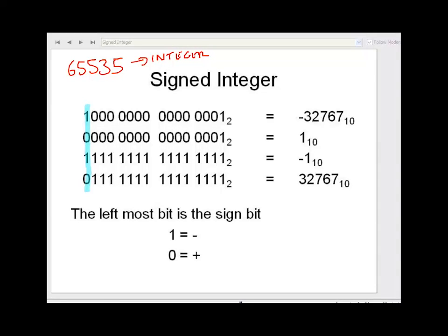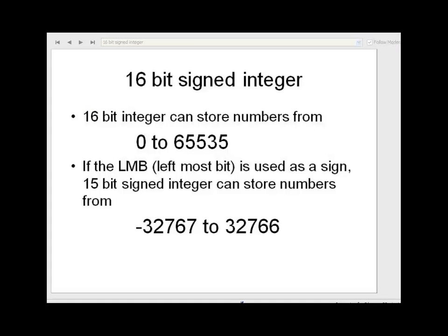Now, that is the other important number that I need you to remember. 32767. That's another magic number. 16-bit locations in PLCs will take up plus or minus 32767. So here's a summary of the important numbers. All of this is leading to just one thing. There are magic numbers which you must remember. The magic numbers are 65535 and 32767.